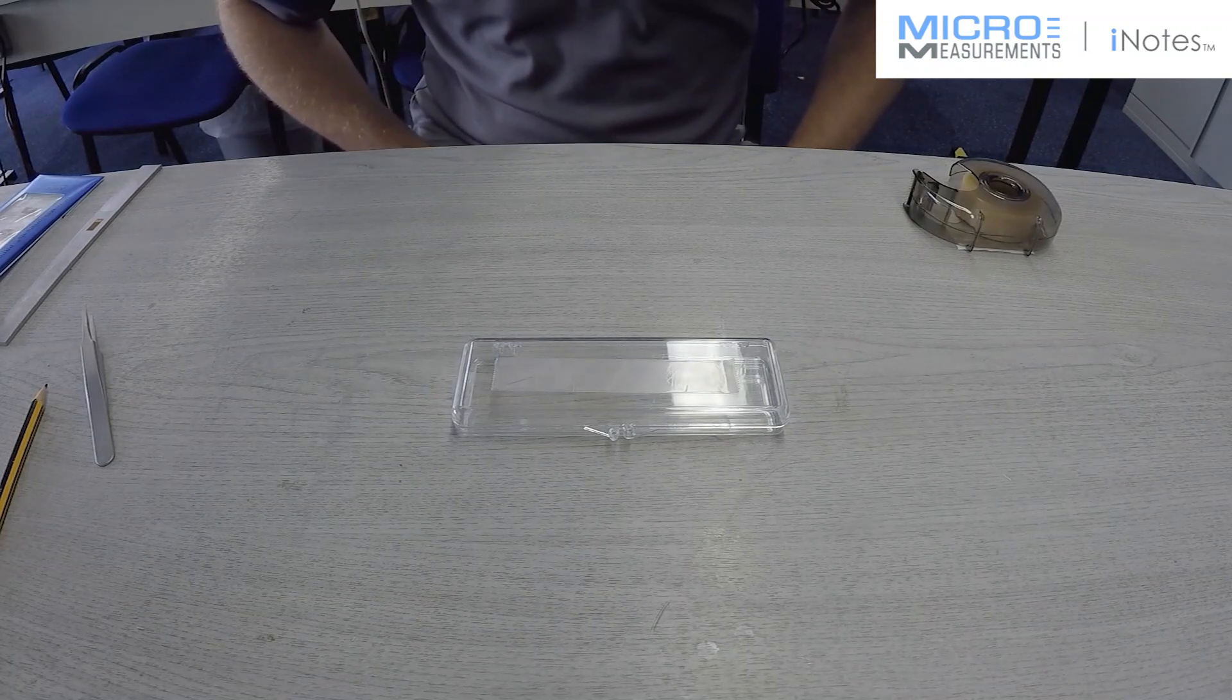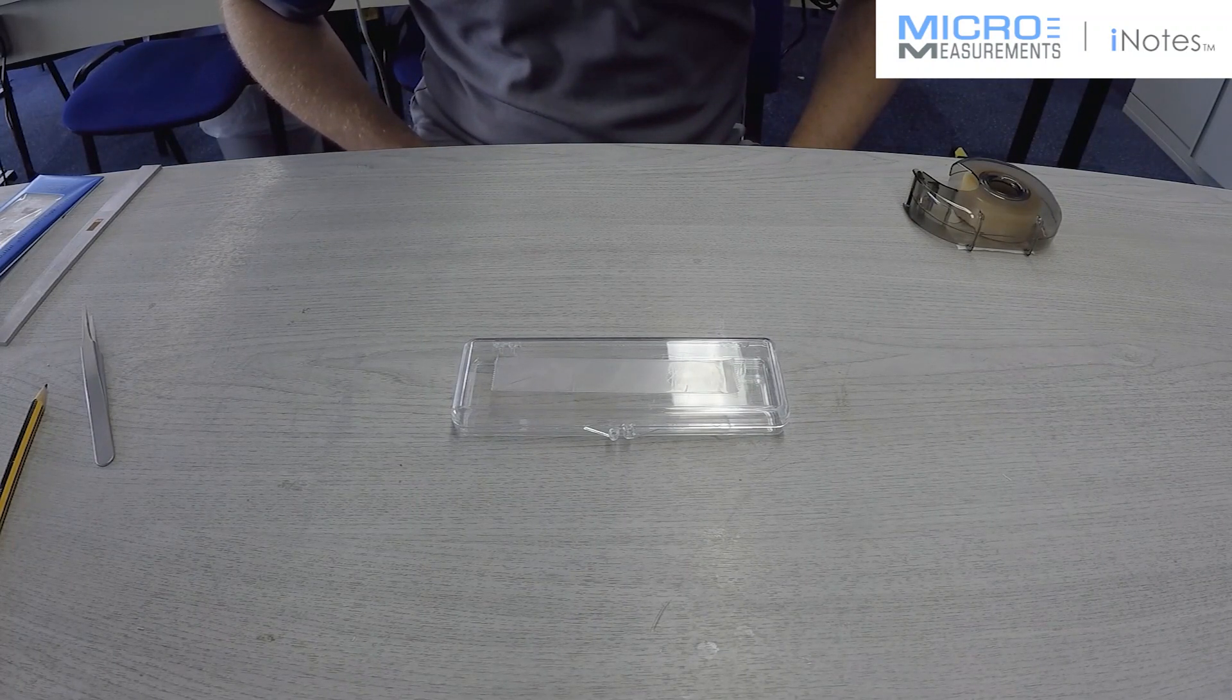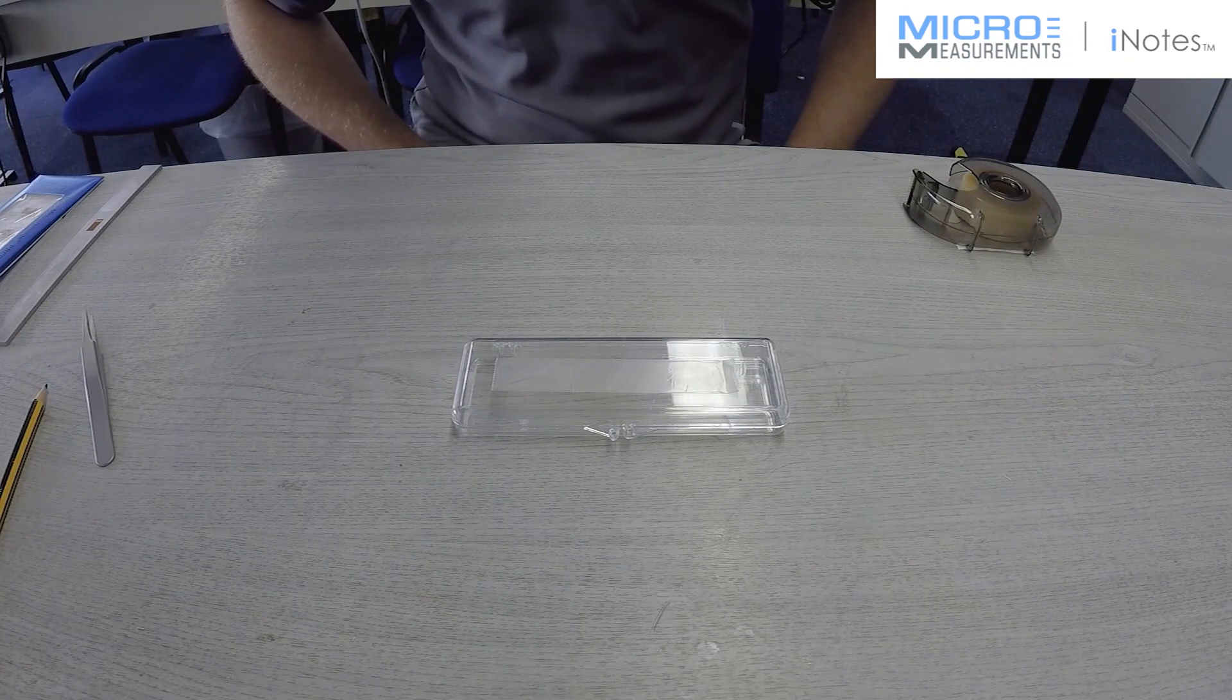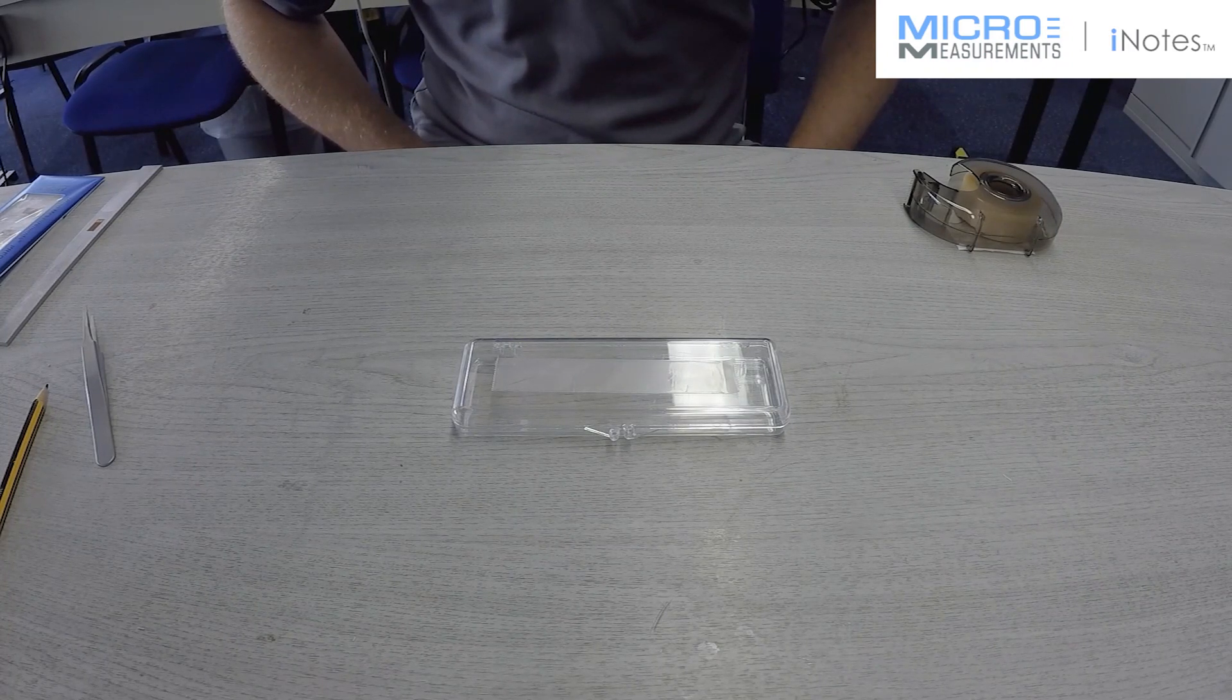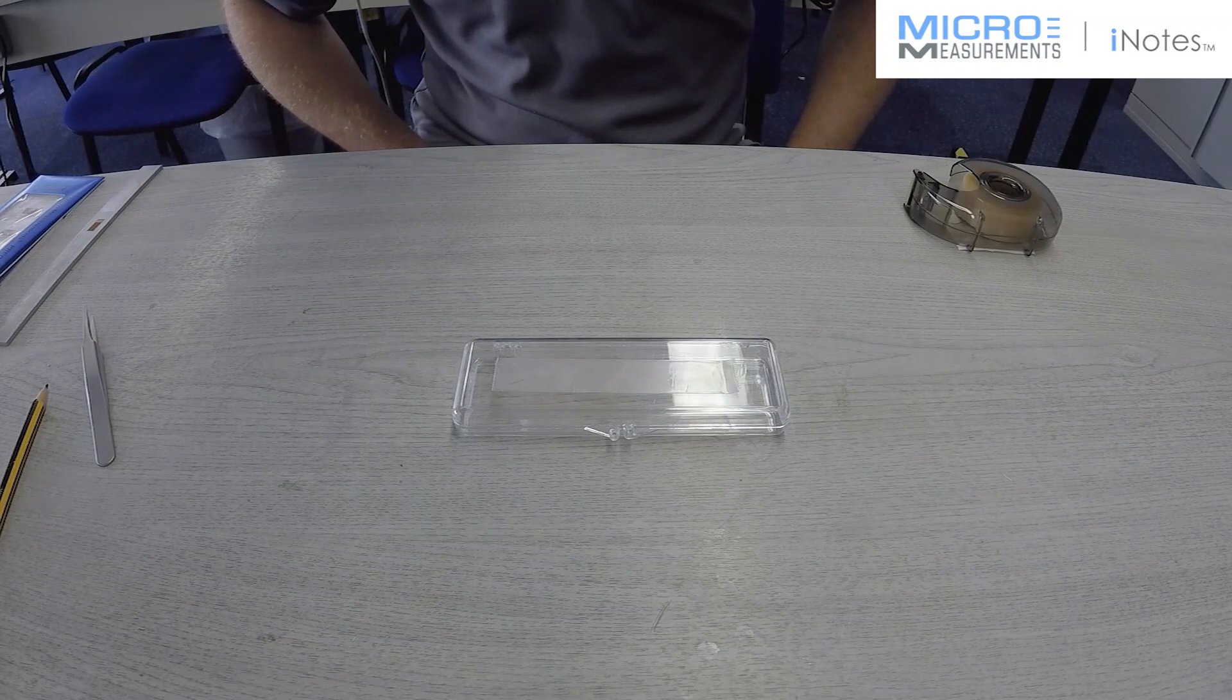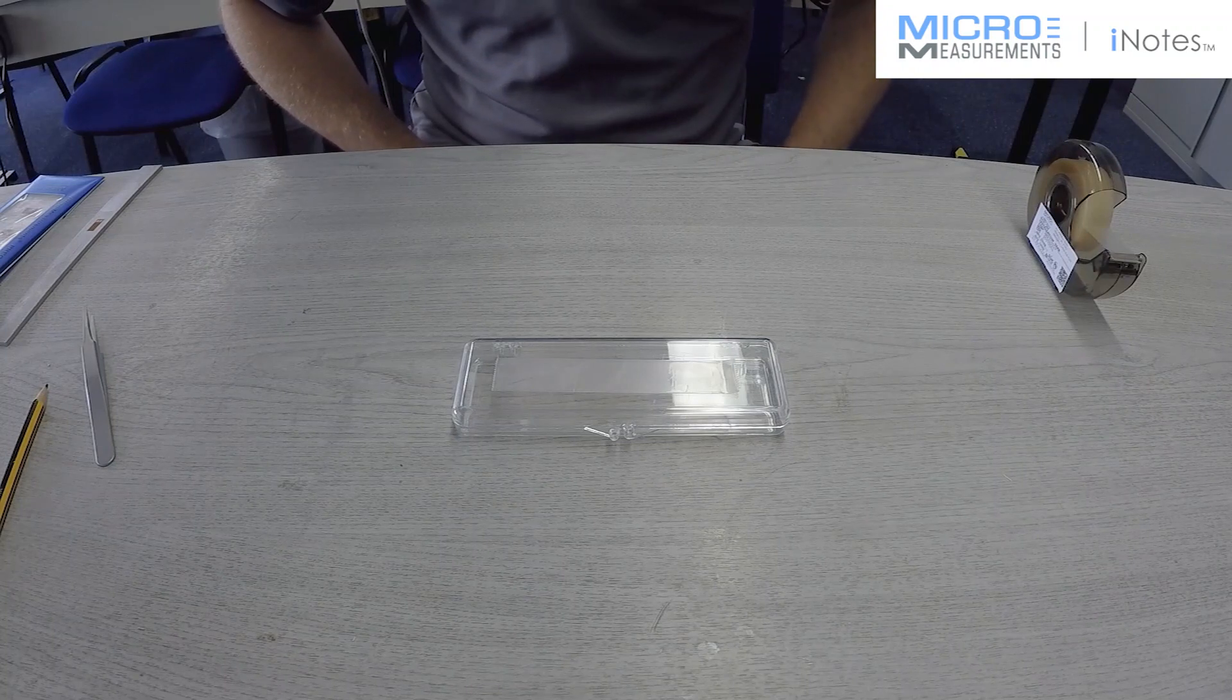And I would just add to that that we know that the tape is compatible with all the micro measurements adhesives because we have tested it and we know that from a room temperature cure to a high temperature cure, maybe even at 100 degrees C or greater, that this tape when it cools back down and you're ready to remove it, it's going to come off cleanly and not contaminate the strain gauge installation.